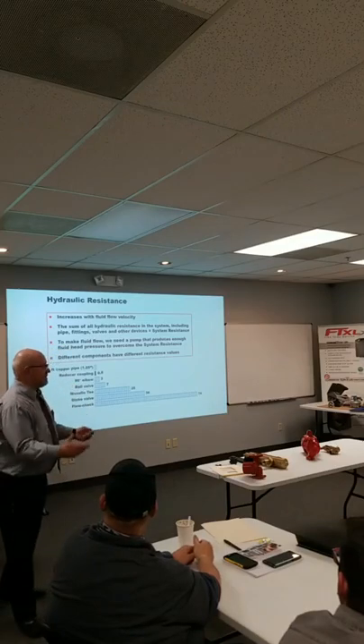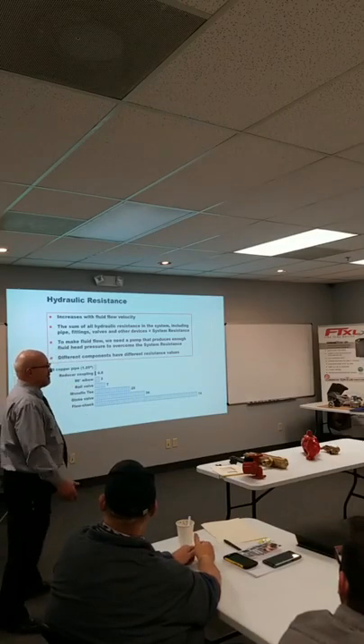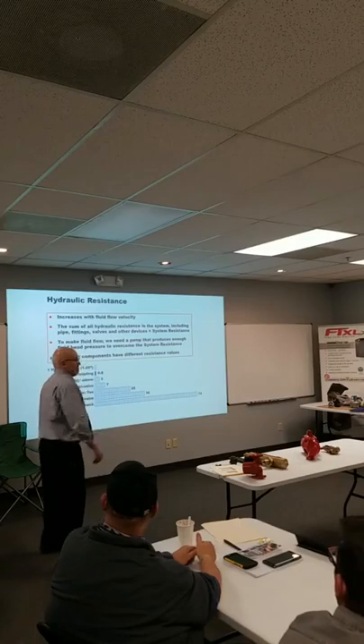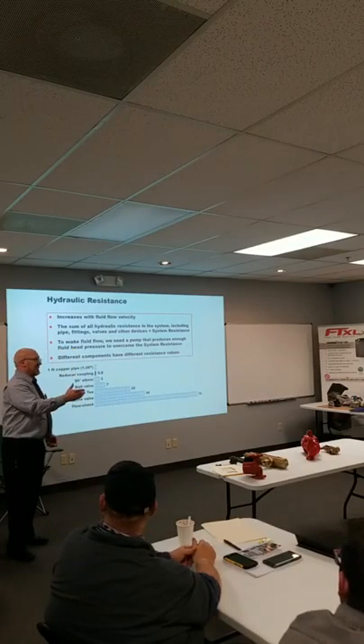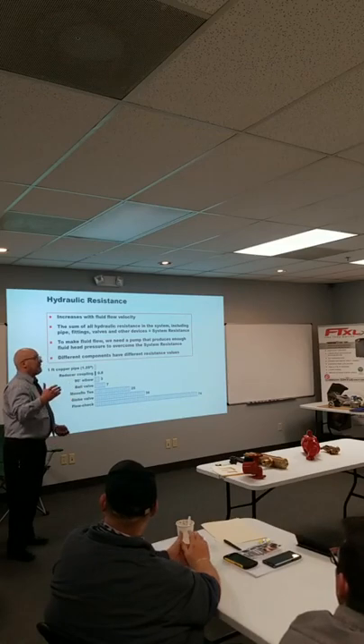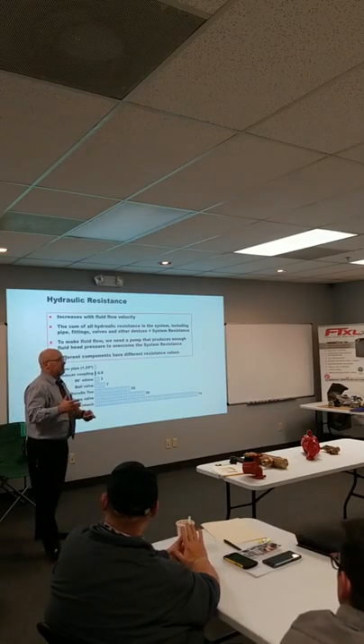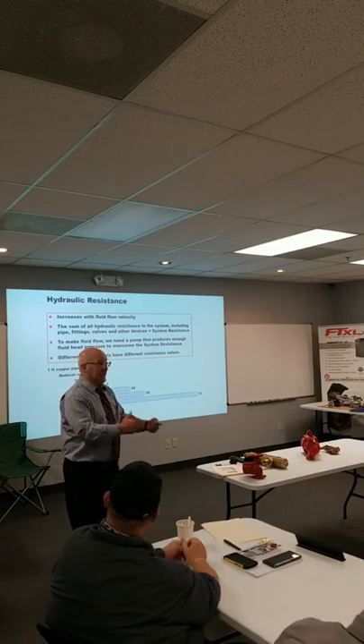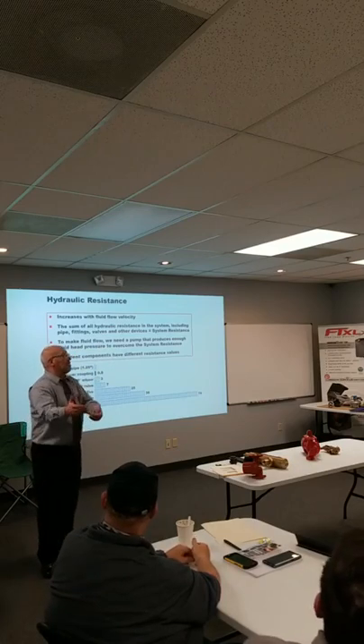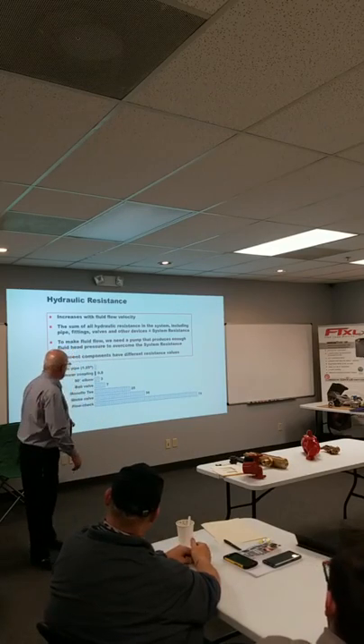Well, it's not fully full flow. Okay, there's a pressure drop. Some have 40%, 60%. You know, they have different valves. In plumbing, we don't use full port ball valves most of the time. But in heating systems, we want you to use full port ball valves because again, the more resistance you have, the more pump power I need to overcome it.